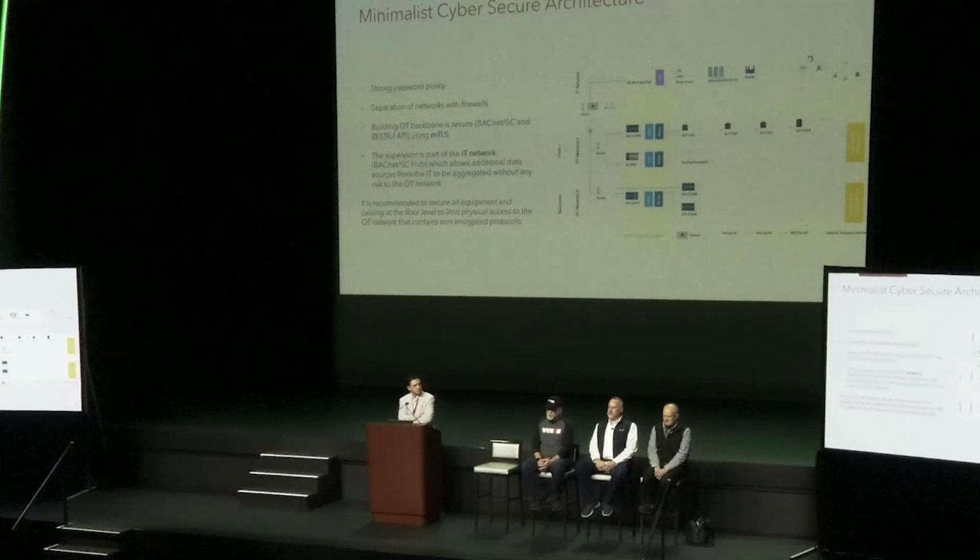I think there are some pretty big management hurdles that all of us have already alluded to, and I think ASHRAE is trying to solve some of those problems. There's a specification that was adopted back in September or October last year that spells out how a BACnet SC device should generate a certificate signing request, or what the APIs are to be able to do that. Today, unfortunately, all of the different manufacturers have different ways of managing certificates in their own devices.